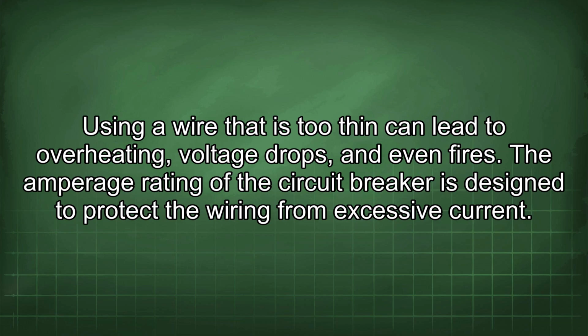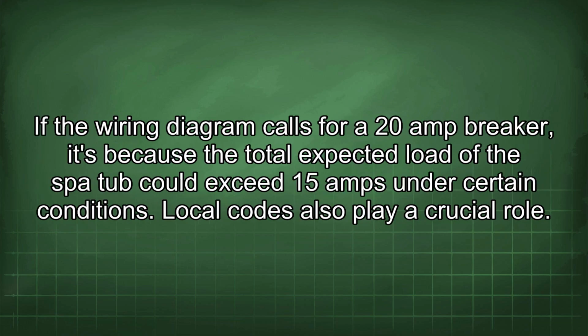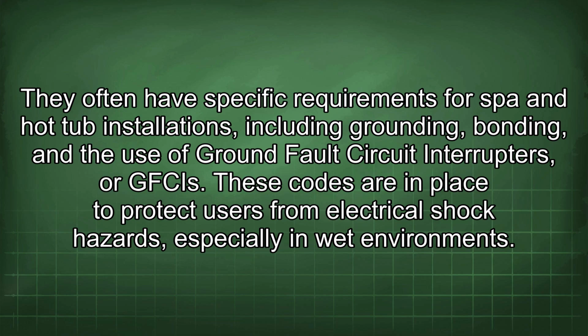The amperage rating of the circuit breaker is designed to protect the wiring from excessive current. If the wiring diagram calls for a 20 amp breaker, it's because the total expected load of the spa tub could exceed 15 amps under certain conditions. Local codes also play a crucial role. They often have specific requirements for spa and hot tub installations, including grounding, bonding, and the use of ground fault circuit interrupters, or GFCIs. These codes are in place to protect users from electrical shock hazards, especially in wet environments.